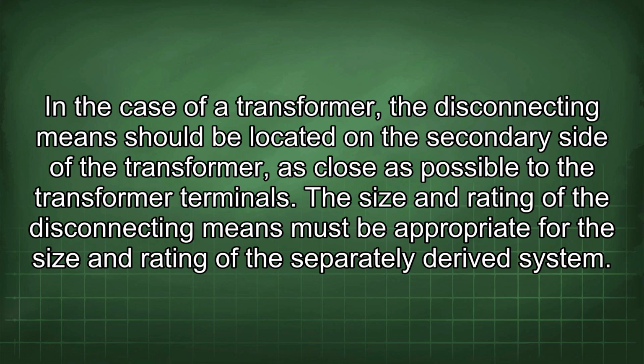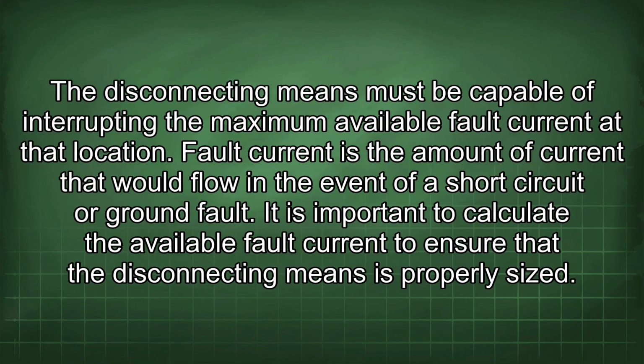The size and rating of the disconnecting means must be appropriate for the size and rating of the separately derived system. The disconnecting means must be capable of interrupting the maximum available fault current at that location. Fault current is the amount of current that would flow in the event of a short circuit or ground fault. It is important to calculate the available fault current to ensure that the disconnecting means is properly sized.